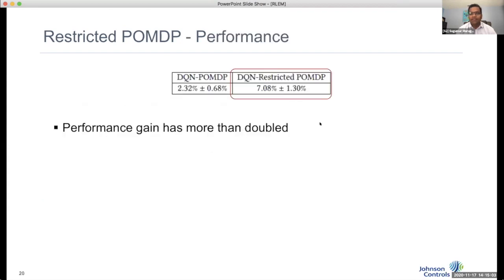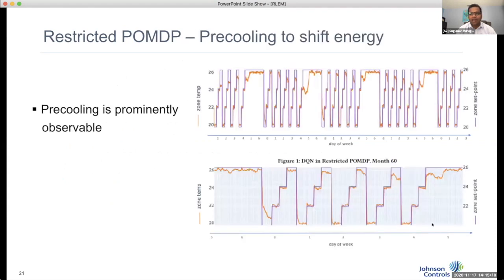We find we get about 2 to 3 times increase in performance gains, which is what you're seeing here. Looking at how this performs, it does pre-cooling around midnight, going to the lowest temperature, and then around 7 a.m. when occupants start coming in, it holds the lowest temperature for that period, which is 22. Then when the on-peak tariff kicks in, we go to the highest temperature. So it does pre-cooling pretty effectively just using time of day.